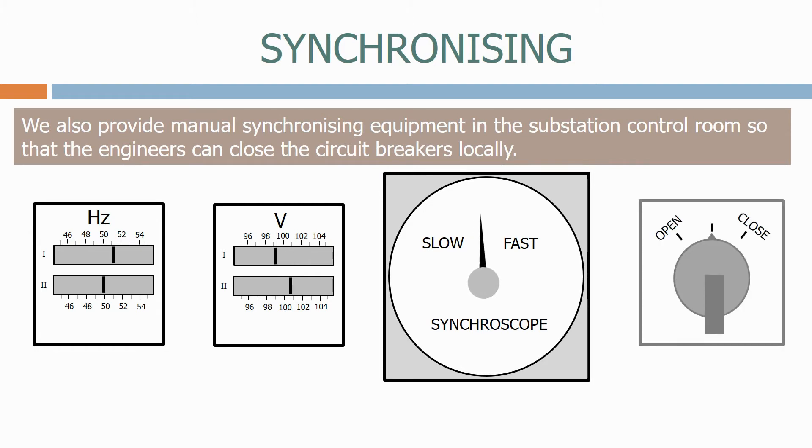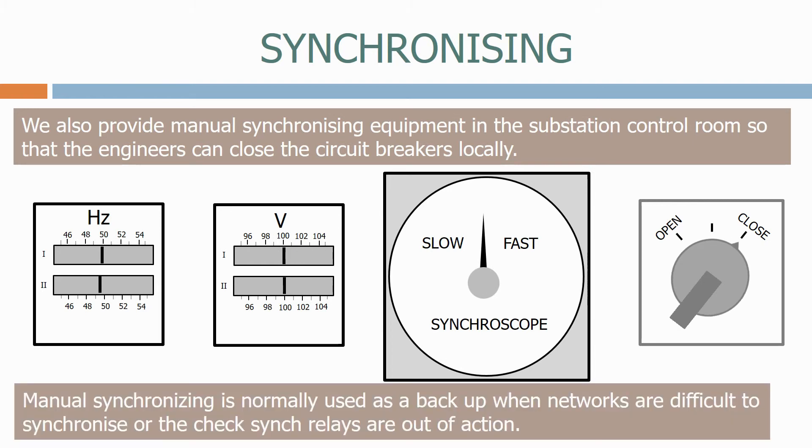The operator watches all three meters carefully and when they think they are close enough, they manually close the circuit breaker. Manual synchronizing is normally used as a backup, when networks are difficult to synchronize or the check sync relays are out of action.